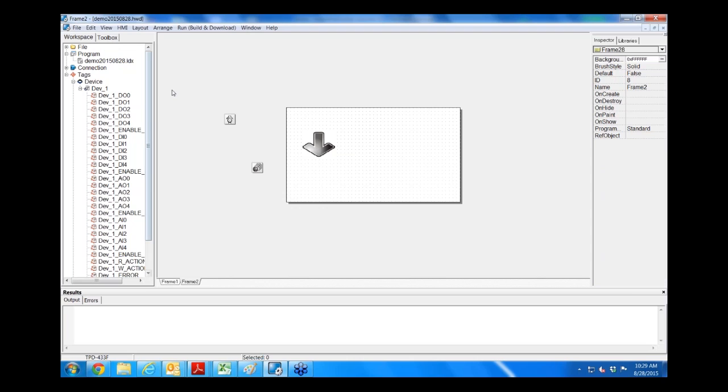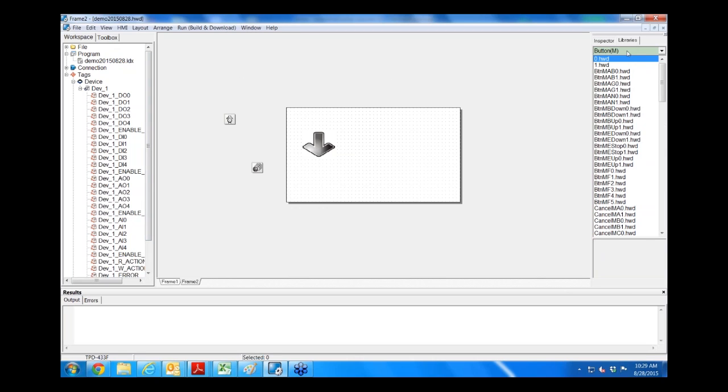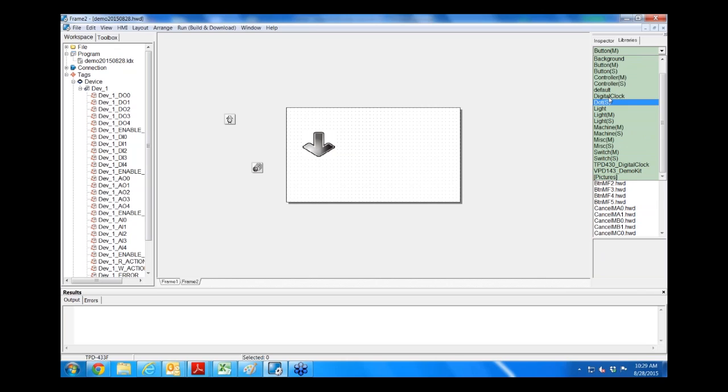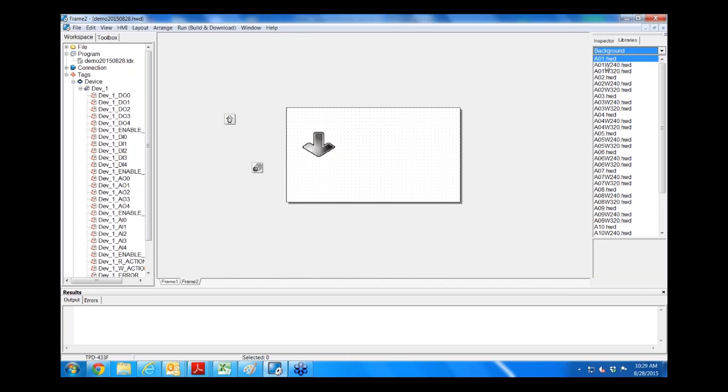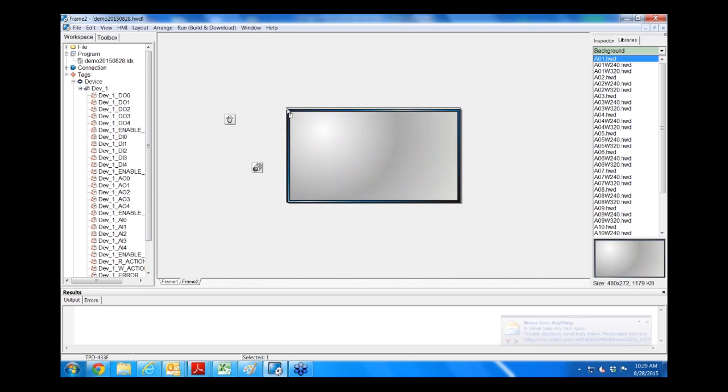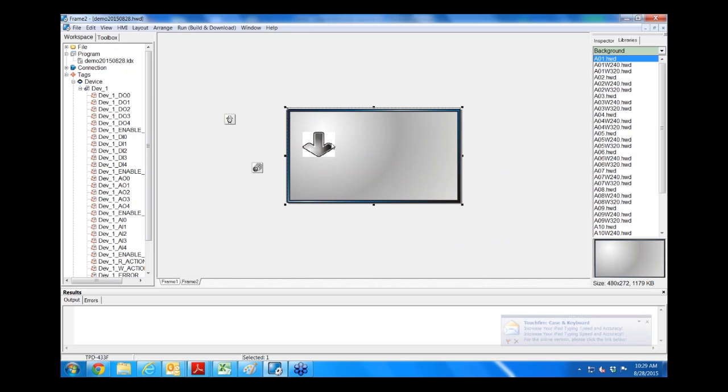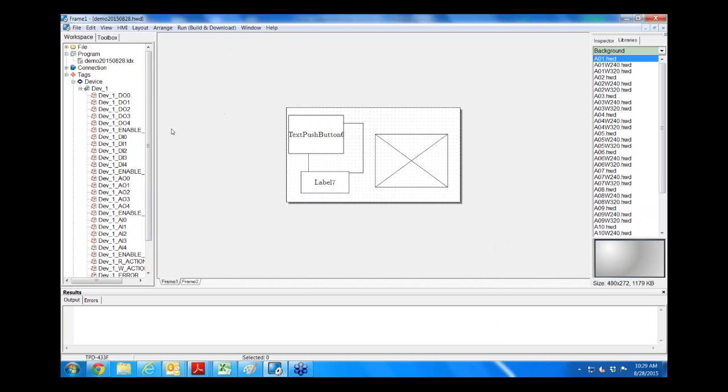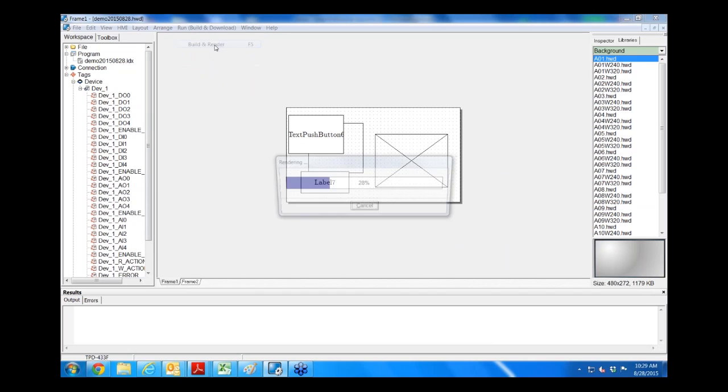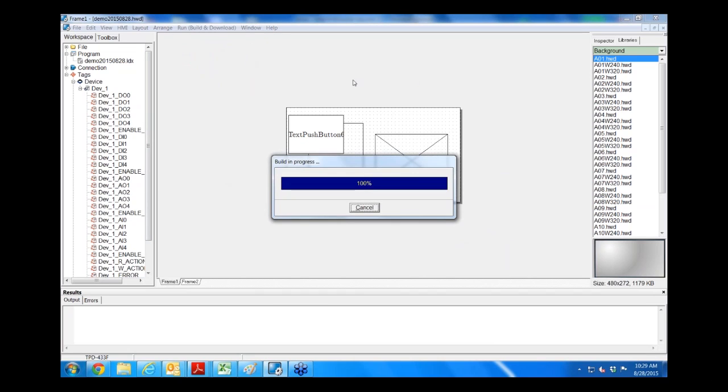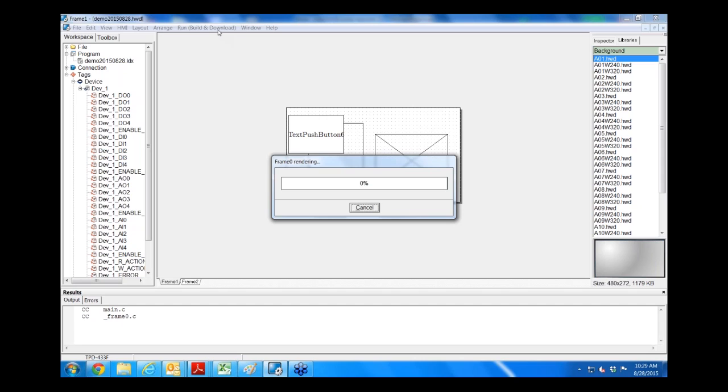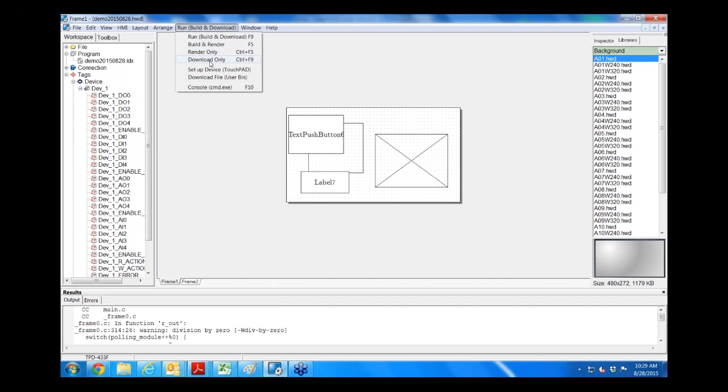Now when you run your project and transfer to the touchpad, your logic will be associated with the tags created in the device and the variable tags. And you can draw a nice picture here. Say, for instance, I want to put a nice background here. Let's just go to our library and we have some background images. Whatever background you choose over here will be here. You just simply drag it. And since we don't want to hide the arrow, we'll send this to the back and you can see the arrow there. Once you've created your project and you're happy with what you see on your screen or screens, then you can do file, build and render to see if you have any errors. It will convert the file to an HXP file and you can use control F9 or click download only to download to your touchpad.